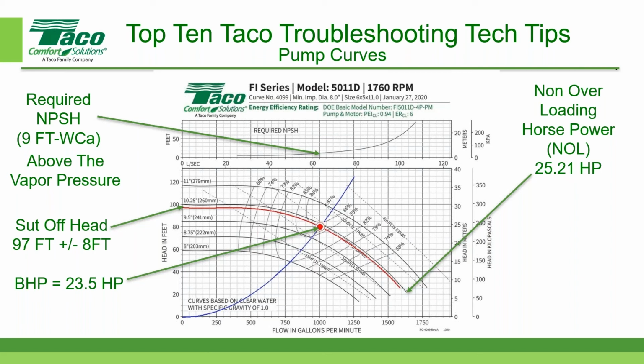volts times the amps, and I divide by 1,000 because volts times amps gives you watts, and I have to convert that into kW. That would give me the kW, and then I have to divide that once more by 0.746 to convert it into horsepower. And if the horsepower came out to roughly 21 horsepower, then I know that I have another piece of data that's starting to point to the fact that the reason I'm not getting the flow is because there's more resistance in the system than what was originally anticipated.